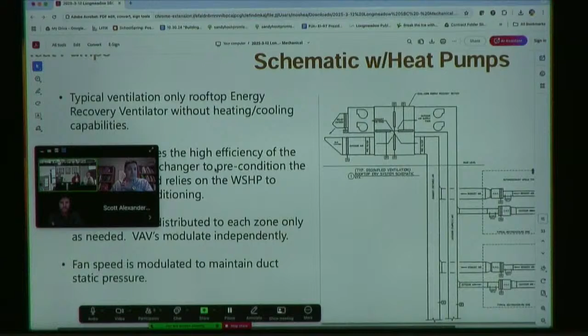And then this slide gives a little overview of how the air-based system is laid out. So you have a roof-mounted energy recovery unit that has both outdoor air and exhaust air components to it. Basically every individual zone gets a variable air volume box to control the ventilation air that's either extracted from or delivered to each individual zone. So if you have a classroom, for instance, each classroom gets a water source heat pump. That water source heat pump will completely recirculate the air within that specific classroom, but the ERV will provide outdoor air directly to that zone and extract exhaust air directly from that zone. And then that's individually controlled.